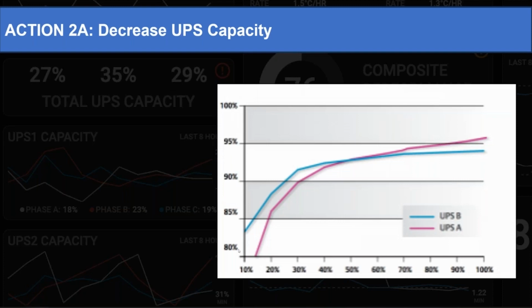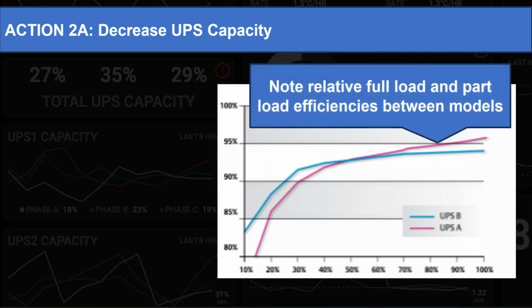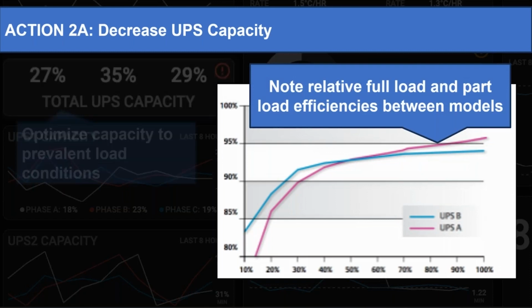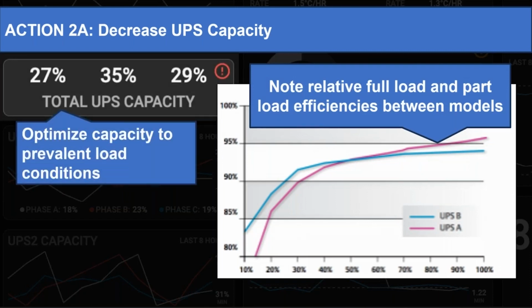And the second step we're going to take is load balance. Normally, if this is a load chart coming from Energy Star UPSs, of course, the form of the trend will be more or less the same. The numbers will vary on type, size and manufacturer. In these two, you can see if a UPS has a 30% load, it has an 87% efficiency. And if you go to an 80% load, you will run up to 93. So you can see this is a normal trend, and normally when you come above 80, it will decrease a little bit again. So you know your most efficient part will be around 80% load. So detaching a part of the UPS capacity will help you to improve your performance.